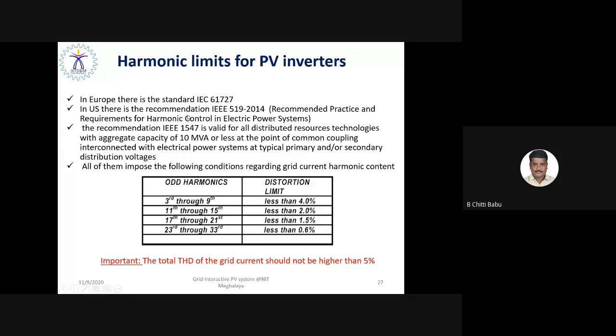Right? As far as the harmonic limits for PV inverters are concerned, in Europe we follow the standard called IEC 61727. IEC stands for International Electrotechnical Commission, which is based in Geneva, right? And in the US, there is the recommendation IEEE 519/2014 standard, the recommended practice and requirements for harmonic control in electrical power systems, including steady state operation. And the IEC is exclusively for industrial operation, for both steady state as well as transient. Okay, we still have another standard, IEEE 1547, for DER integration with capacity up to 10 MVA.